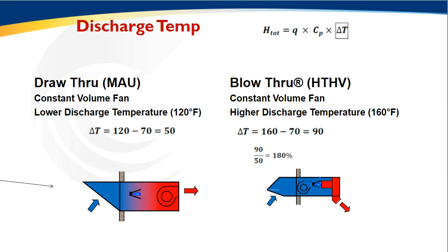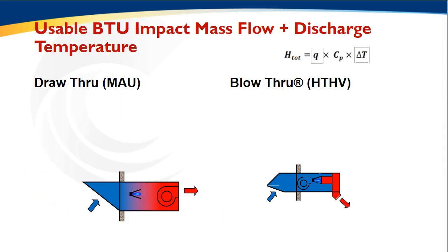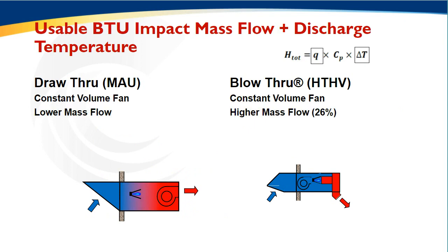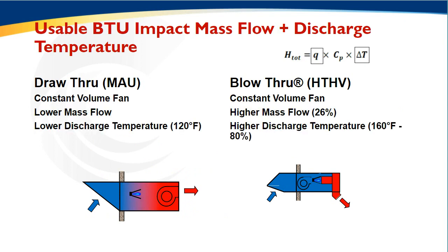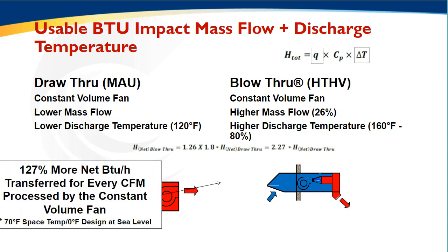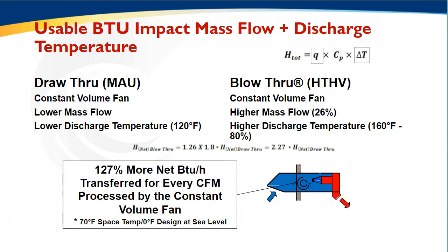Massive difference. And if I combine those two key factors now, let's bring back that higher mass flow rate with processing cold air, more dense air with the blower in the cold airstream, and now by having an additional 80% of net BTUs caused by the higher discharge temperature, adding my 26% and 80% factors, I now have 127% more net BTUs transferred for every CFM. If I hold my CFM constant, comparing these two systems, the HTHV can deliver 127% more ability to heat.